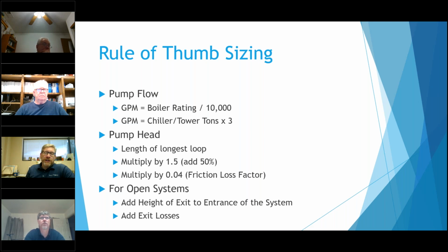For open systems, I try to add the height of the exit into the entrance of the system. For towers, a lot of times that's just 10 feet that I add to it. And then any exit losses, again, we're just estimating here. A lot of times, if it's a tower, I'll add like 5 to 10 pounds. If it's a pressure booster, some of those get to be like 20 to 40 pounds, with some of those lower flow fittings and shower heads and faucets and what have you.